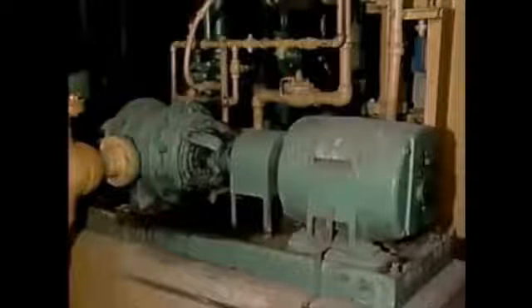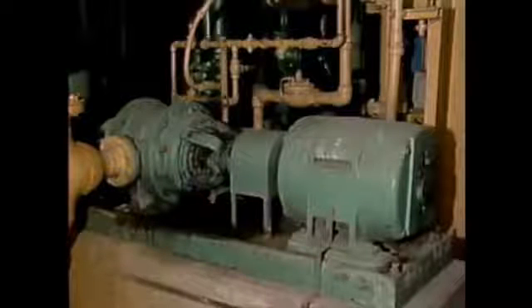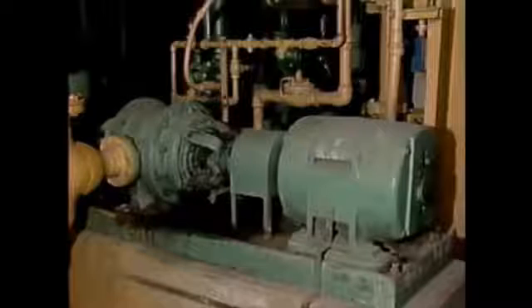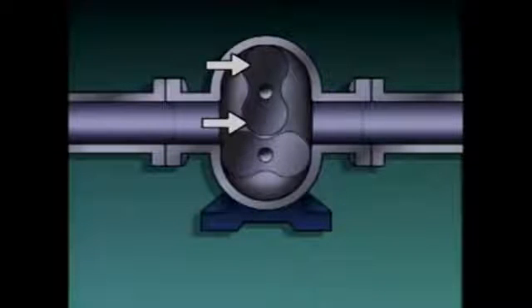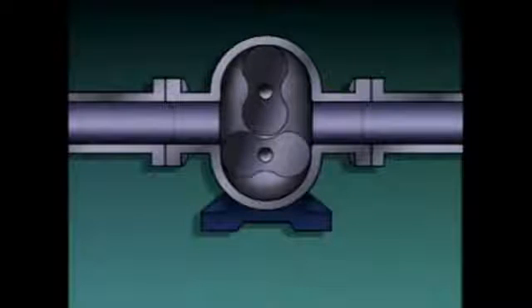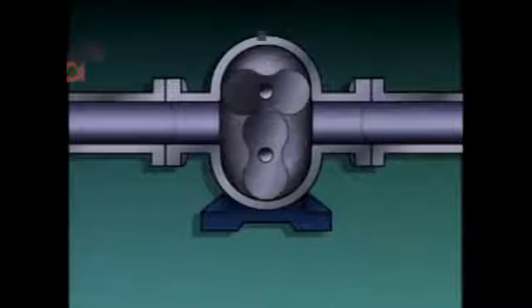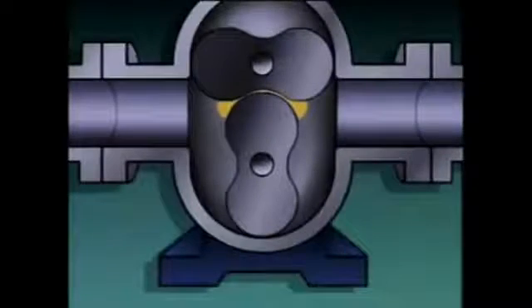Another type of rotary pump that moves liquid by trapping it in spaces and forcing it out is a lobe pump. Lobe pumps use lobes instead of gears to move process liquids. The pump shown is often called a two-lobe pump because each rotor has two lobes, but lobe pumps can have as many as three or four lobes on each rotor depending on their design. The lobes are made so that they rotate closely together, forming a seal between them that prevents leakage of liquid back to the suction.